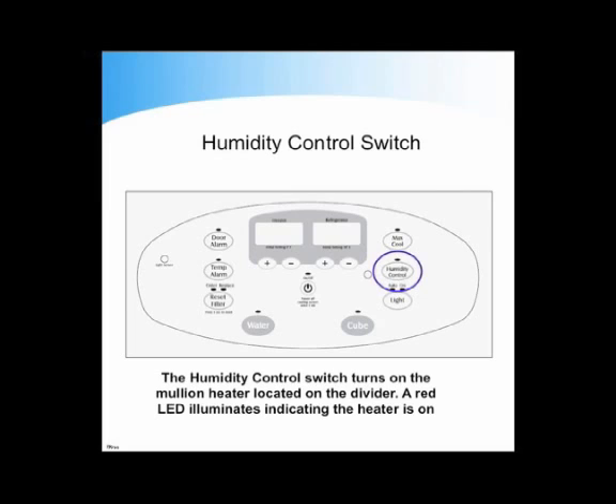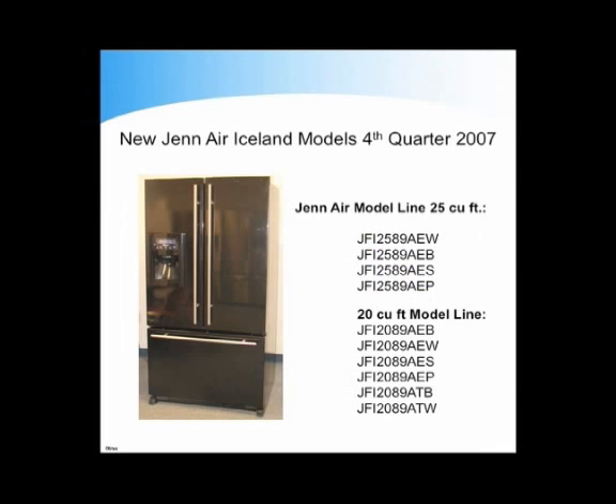The second mode is on 100% of the time. Changing to this mode can only be done through the service mode. After this change, pressing this key will still toggle the feature on and off, but the heater will be on 100% when the feature is active. The initial state of this feature will be off. The default on mode is the heater cycling with the compressor. The state of the switch and mode will need to be retained in non-volatile memory.